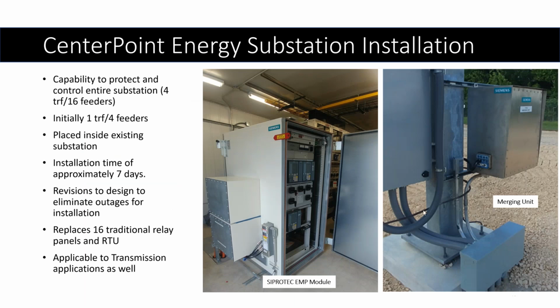So here's the completed installation of the EMP module inside of the substation. As you can see, it's fitting right next to the existing lineup of panels that were in the substation, and it actually replaces what would typically be 16 individual feeder or transformer panels with one module. And the way that we're able to do that is because of the use of fiber optics. All of the spacing is much closer. And then additionally, we can do multiple protection schemes within one relay. So we still have full redundancy using multiple relays, and then the merging units themselves have some protective capability, but it allows us to shrink the size of that protection and control package while hardening it at the same time. Overall, the installation time was roughly 7 days because we're able to do pre-testing in a digital workbench and then we move into the live substation after that. Next slide, please.